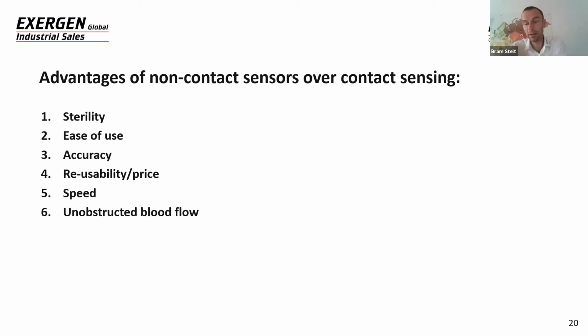Accuracy is a big thing, especially if you use contact probes that you mount on the outside of a tube. If the contact is not good, because a contact sensor will measure its own temperature. So if the contact sensor is not a good representation of the target, if it's not mounted well, then you don't get a good reading. With IR sensors, it doesn't really matter if the distance is a bit shorter or longer. It doesn't need to make contact, so it's very, very accurate.